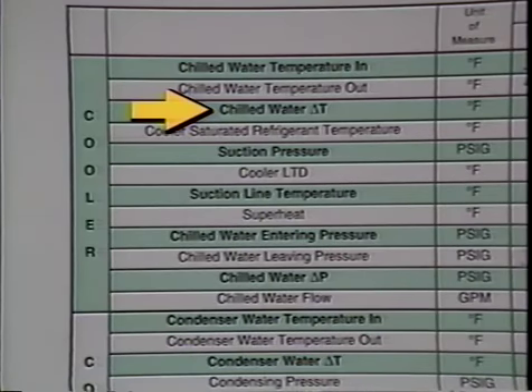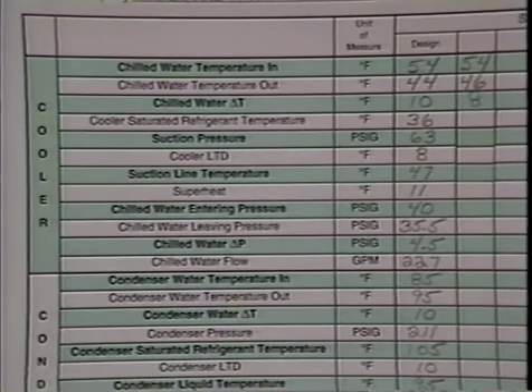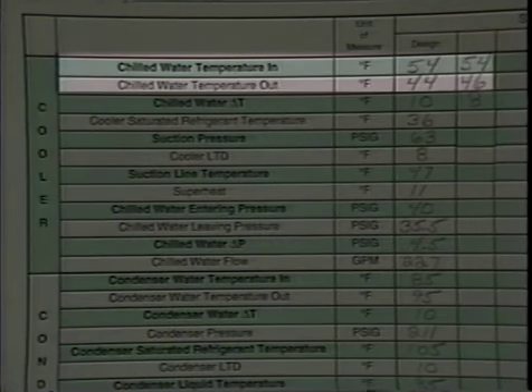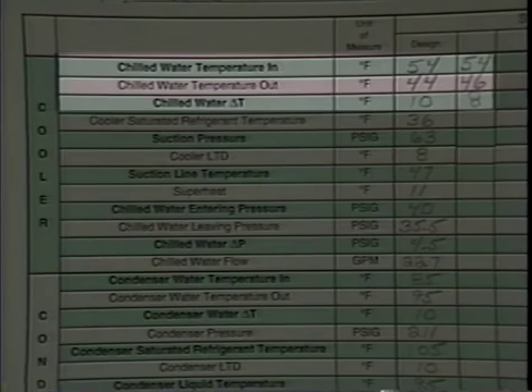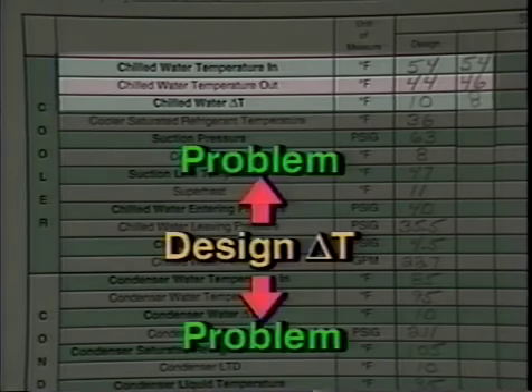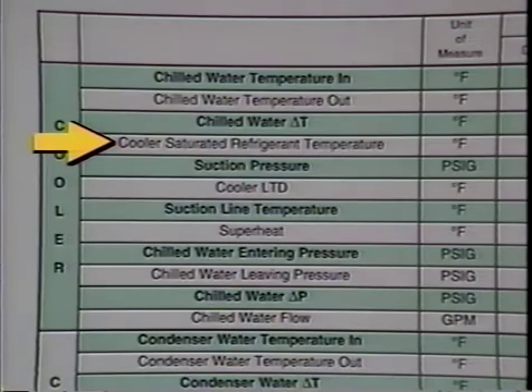Chilled water delta T. Now we can determine the chilled water delta T, which is the difference between the entering and leaving chilled water temperatures. Chilled water delta T provides an indication of system capacity. If it's above or below the design delta T, then a problem may exist. More about this later.